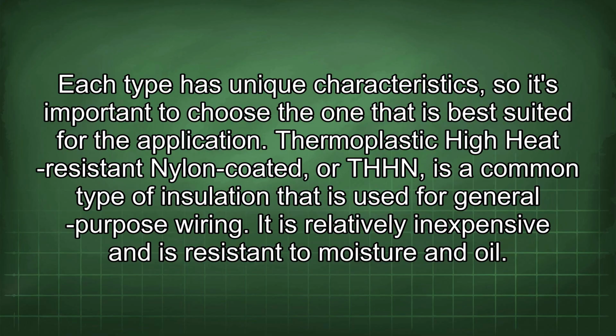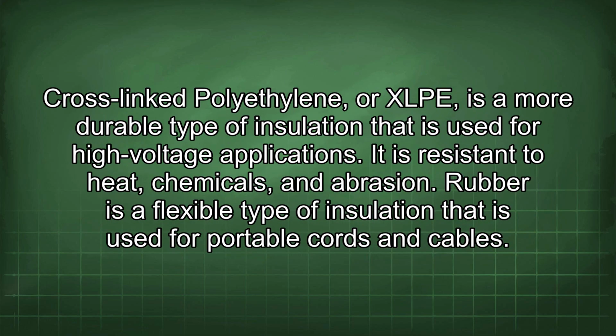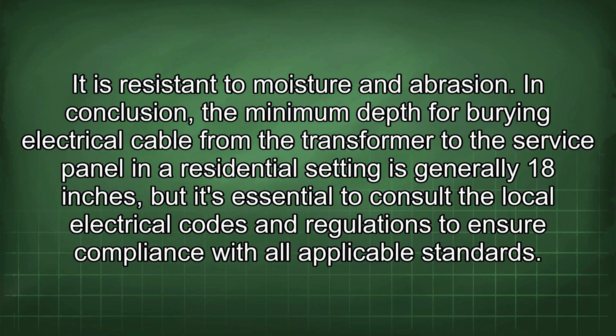Thermoplastic high heat resistant nylon coated, or THHN, is a common type of insulation that is used for general purpose wiring. It is relatively inexpensive and is resistant to moisture and oil. Cross-linked polyethylene, or XLP, is a more durable type of insulation that is used for high voltage applications. It is resistant to heat, chemicals, and abrasion. Rubber is a flexible type of insulation that is used for portable cords and cables. It is resistant to moisture and abrasion.